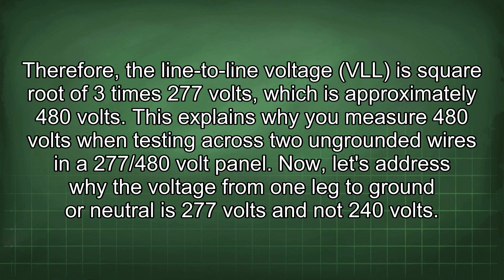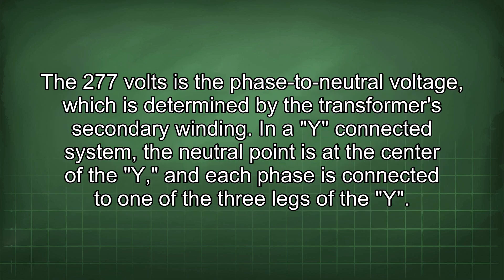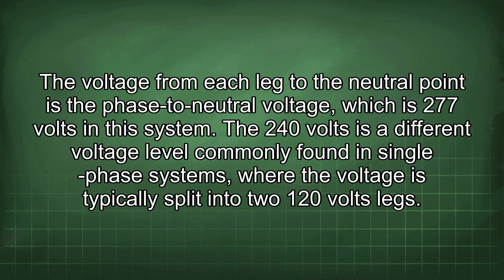This explains why you measure 480 volts when tested across two ungrounded wires in a 277/480 volt panel. Now let's address why the voltage from one leg to ground or neutral is 277 volts and not 240 volts. The 277 volts is the phase-to-neutral voltage, which is determined by the transformer's secondary winding. In a Y-connected system, the neutral point is at the center of the Y, and each phase is connected to one of the three legs. The voltage from each leg to the neutral point is 277 volts in this system.